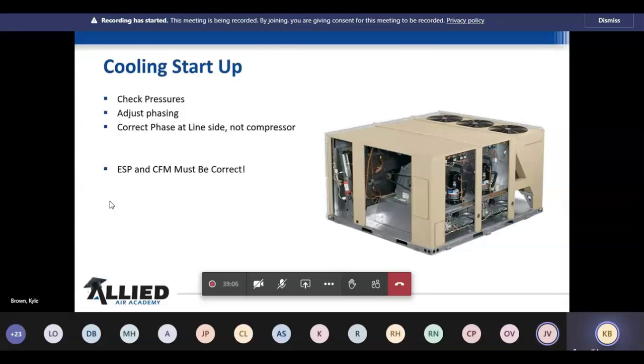And then we may need to adjust the phasing. And again, make sure somewhere we document that the phasing was adjusted, so if the wires don't line up on the diagram like it was from the factory, the next person who goes and works on it will know. If you change it on the line side and not the compressor, then you've got to be careful of your indoor motor as well too. You can't forget about that. So if you correct the indoor motor and then you go to correct the compressors, go back to the indoor blower motor and make sure, and then you're going to get tired of me saying this, but external static pressure and CFM must be correct.